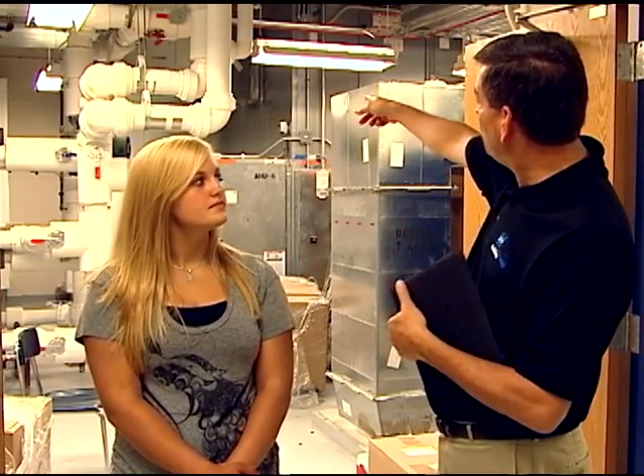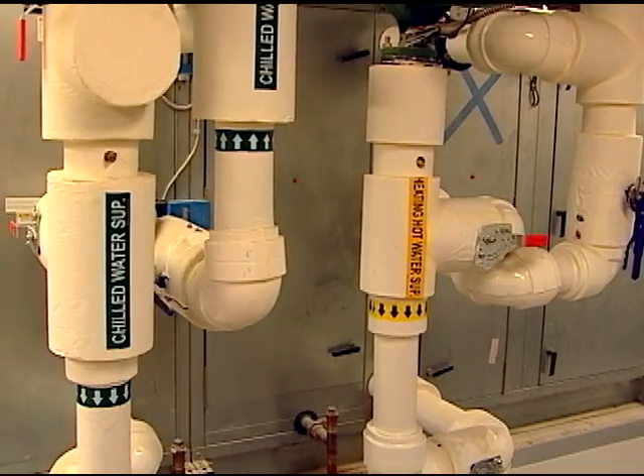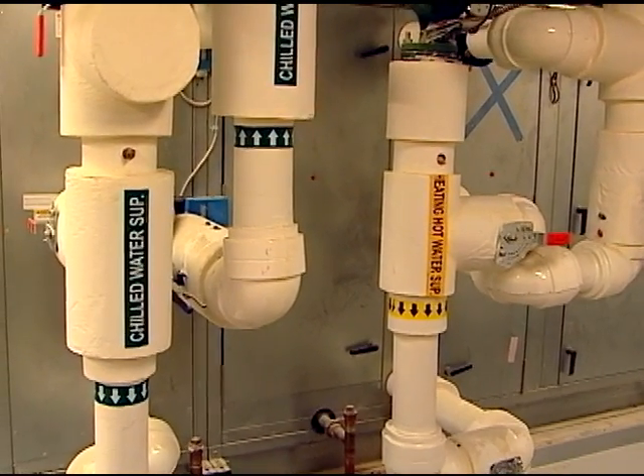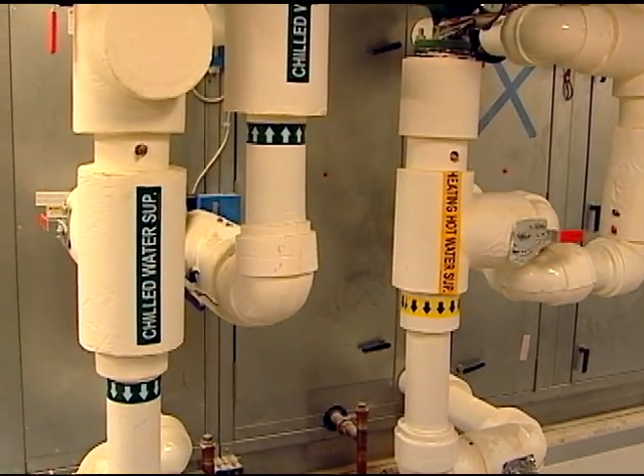In fact, you can see giant air handlers that fit in a room this size, but serve about 8 to 10 classrooms in this building. It takes 5 of these rooms across the building to create all of our environment, but it's a very efficient way to do it. The only thing coming from the central plant is hot and cold water through these white pipes you see behind us, and that's how we get that hot and cold power to these rooms.